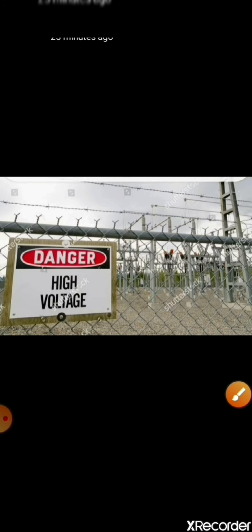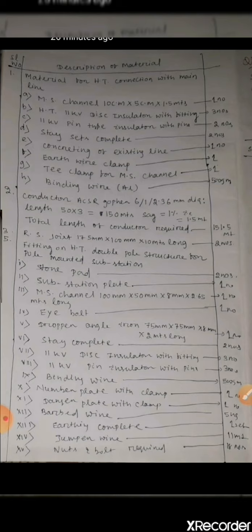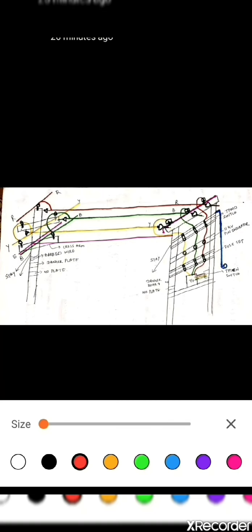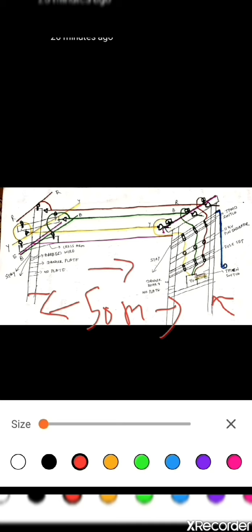And next we will do one problem. The problem is to estimate the cost of a pole mounted substation of capacity 50 kVA transformer operating at 11 by 0.4 kV. The HT line is available about 50 meter from the proposed site. Also make a neat sketch of the pole mounted substation. This is the sketch of the pole mounted substation. And this substation is 50 meter away from the existing 11 kV line. This is the existing pole, and from this pole the connection will be taken to this pole mounted substation.